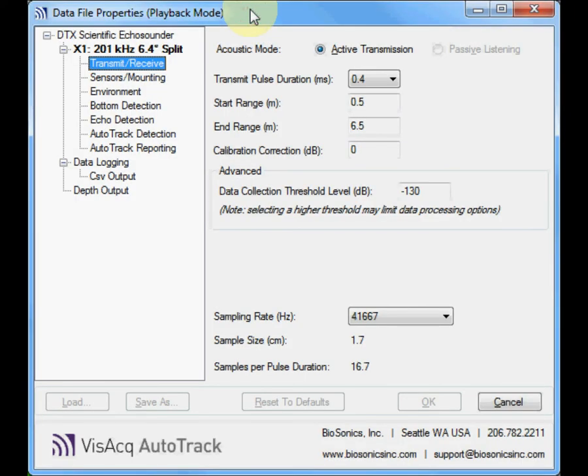Next up is the transmit and receive tab. In here you're going to set your acoustic mode, make sure you're in active transmission. Transmit pulse duration, anywhere from 0.4 to 0.5 milliseconds is recommended. Our calibration data sheet has the theoretical value calculated using a 0.5 millisecond pulse, so anything outside of that may give you a slight difference in target strength. Start and end range, just make sure it's set to where you're going to be able to see the sphere. We do recommend having the calibration sphere anywhere from 5 to 10 meters below the transducer.